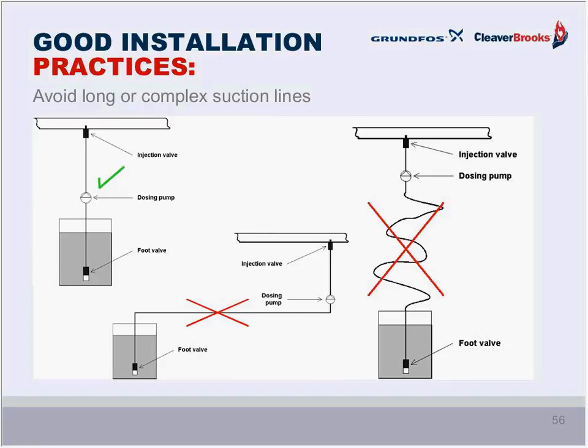Okay, before I wrap up this part of the webinar, I want to take a look at a few good installation practices and some that are to be avoided. These practices will help to assure an optimally performing boiler water treatment program. The check mark next is an ideal installation. Have a straight line of pipe or tubing with a valve, which is basically a check valve, on the suction line. This maintains prime.